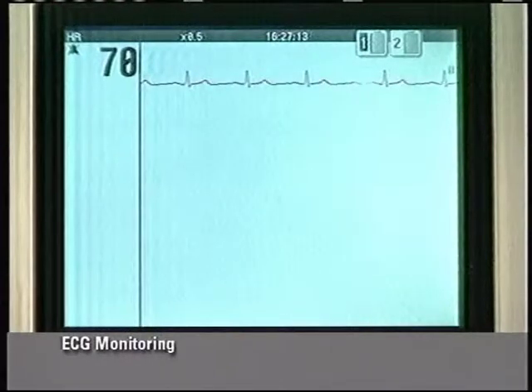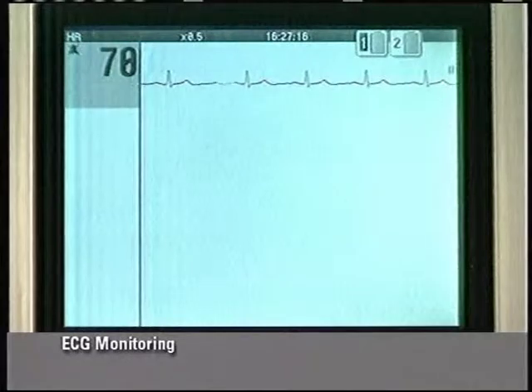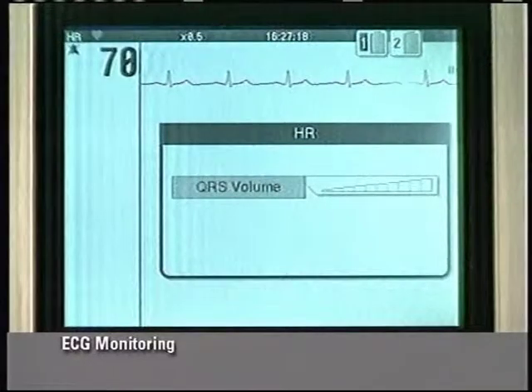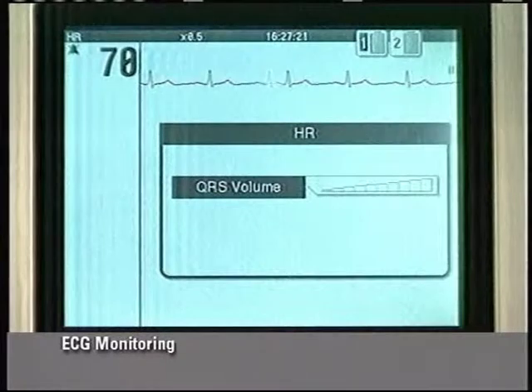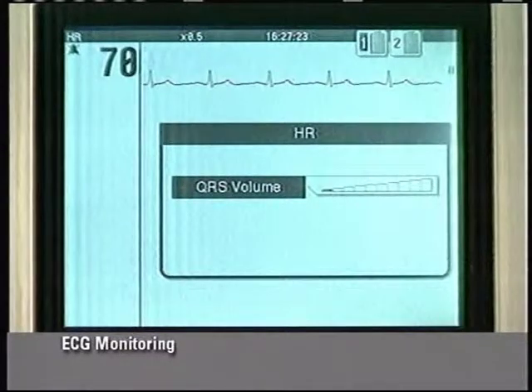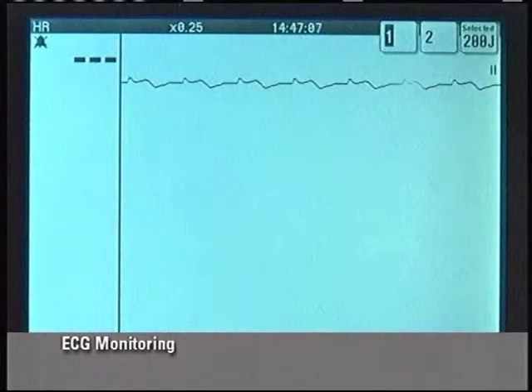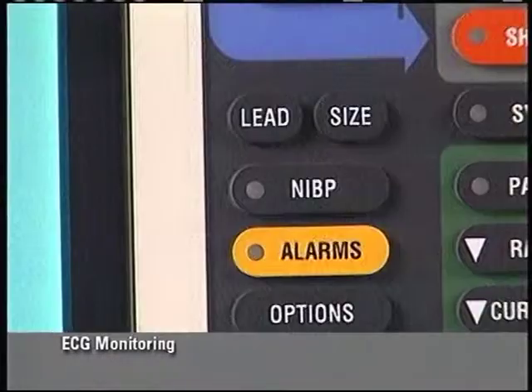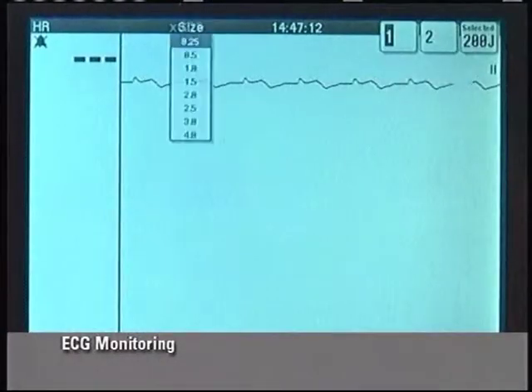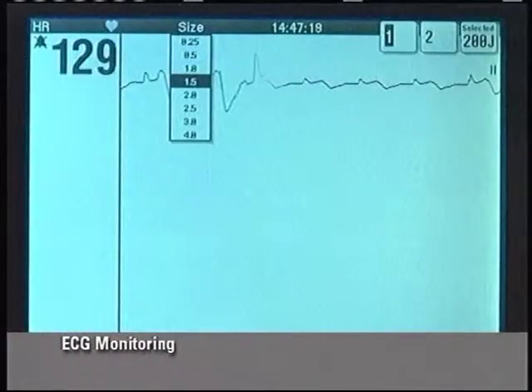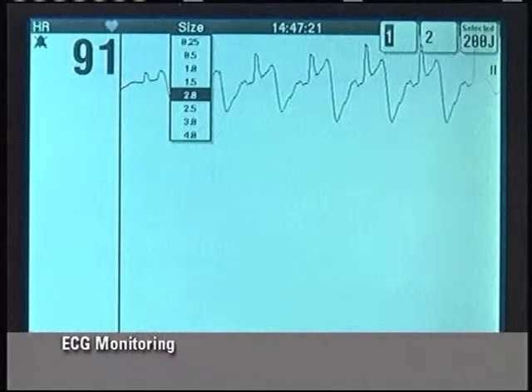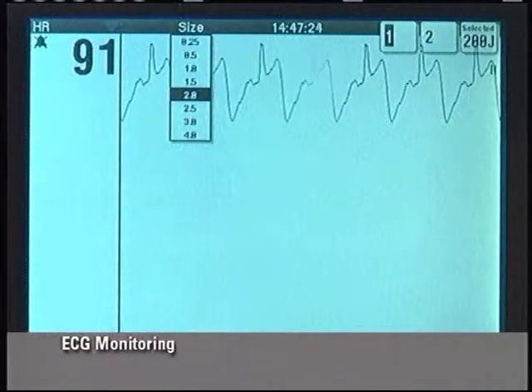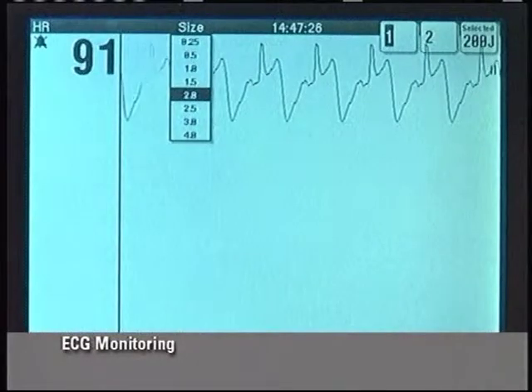To adjust the systole tone volume, highlight the heart rate area, press the selector to display the heart rate menu, press the selector to black highlight QRS volume, then rotate the selector to increase or decrease the systole tone volume. If the heart rate counting is inaccurate, adjust the ECG size. Press the size button. The size menu appears. Continue to press the size button or rotate the selector to change the size. Note that the ECG trace in channel 1 automatically changes as each size is selected.